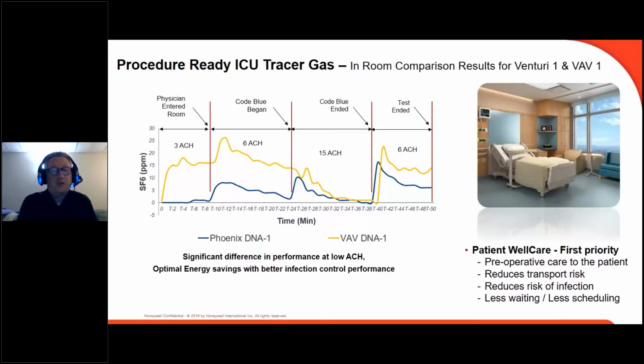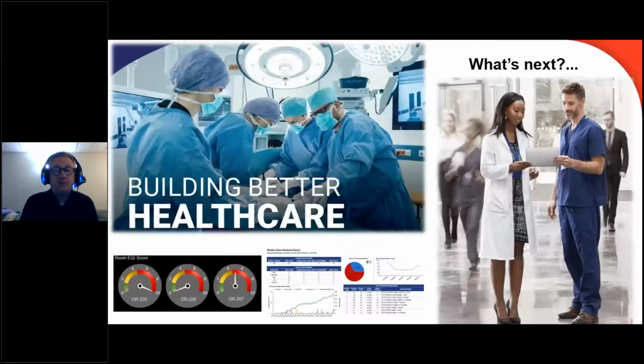So if a code blue situation was to happen, again, from a nurse's station, from a tablet, you can increase the air change rates immediately and get that space cleaned, right? But you have the flexibility now within the system to go from 3 to 15, again, stable transition without compromising directional flow, right? So there's a number of benefits with that. And again, that paper covers a lot of that, but they even saw reduced CFUs around the patient bed. They saw better stable transition times. Again, everything that affects the environmental quality of that space.